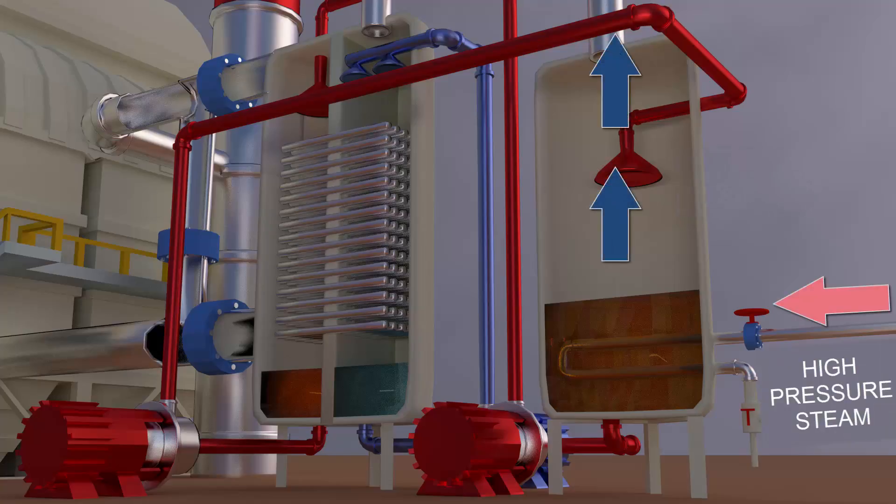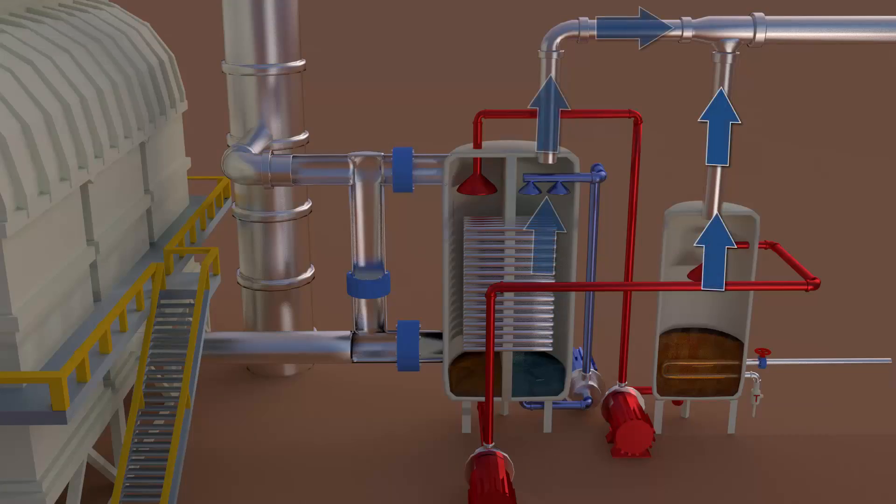In rough terms, one pound of high-pressure steam generates one pound of low-pressure steam. But this stream is doubled in magnitude when combined with the stream that was generated through flue gas scrubbing.